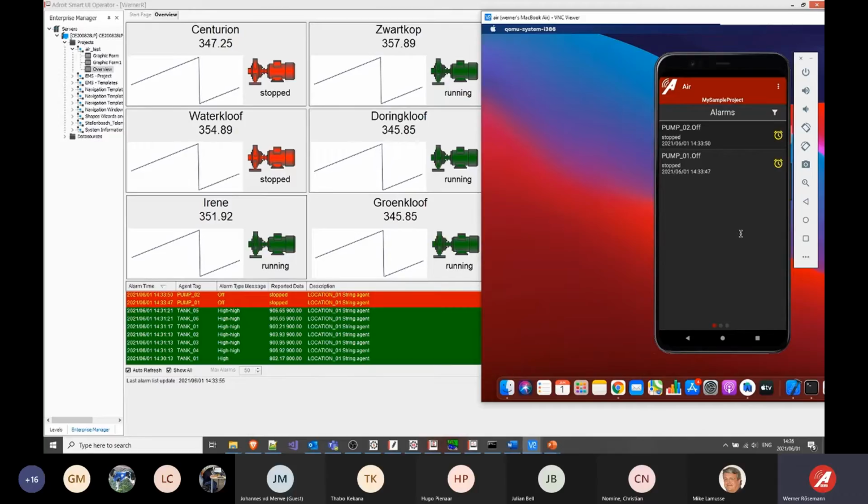We're still only sending the alarms on a deadband of a minute. Same with process data. So the quickest turnaround you're going to get after the alarm occurs or after a process data message is triggered is it'll deliver within a minute of that event.